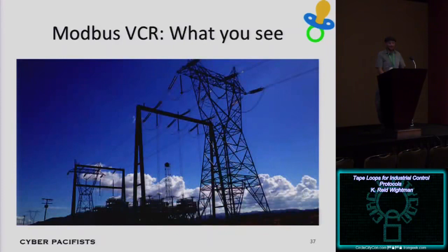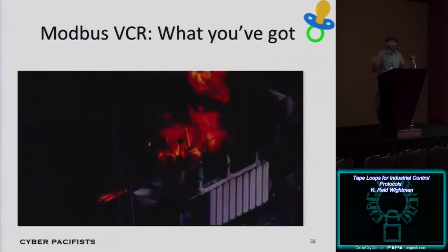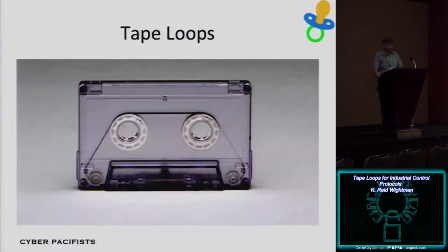With the Modbus VCR, your operator will see the network running fine, the control system going great, even though maybe your transformer caught on fire because a guy shot it with a rifle and the transformer oil leaked out and it overheated. That's the kind of stuff you can hide with the Modbus VCR—though I hate using the fire example, I'm a professional. Also, people are always talking about making SCADA stuff explode, and I don't really like talking about that, but that's kind of what tape loops is about.